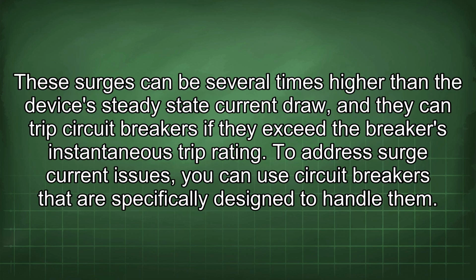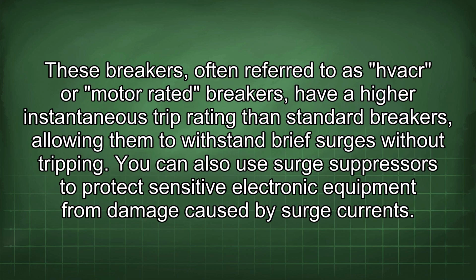These surges can be several times higher than the device's steady-state current draw, and they can trip circuit breakers if they exceed the breaker's instantaneous trip rating. To address surge current issues, you can use circuit breakers that are specifically designed to handle them. These breakers, often referred to as HVACR or motor-rated breakers, have a higher instantaneous trip rating than standard breakers, allowing them to withstand brief surges without tripping.